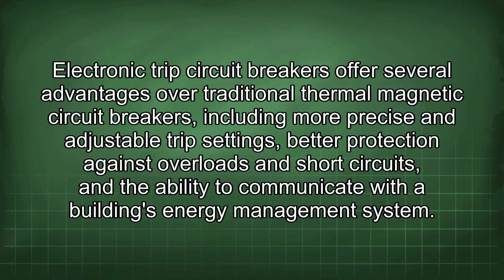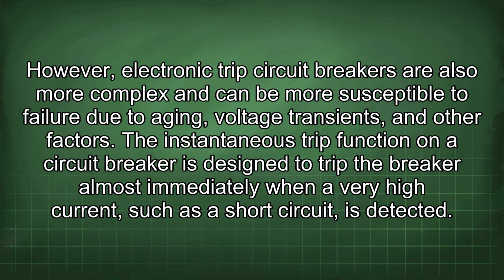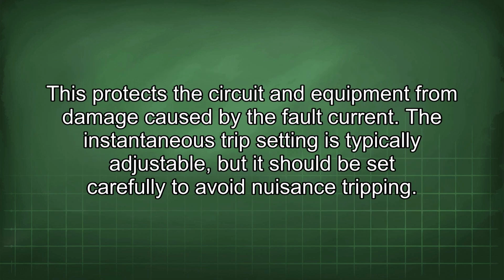Electronic trip circuit breakers offer several advantages over traditional thermal magnetic circuit breakers, including more precise and adjustable trip settings, better protection against overloads and short circuits, and the ability to communicate with a building's energy management system. However, electronic trip circuit breakers are also more complex and can be more susceptible to failure due to aging, voltage transients, and other factors. The instantaneous trip function on a circuit breaker is designed to trip the breaker almost immediately when a very high current, such as a short circuit, is detected. This protects the circuit and equipment from damage caused by the fault current.